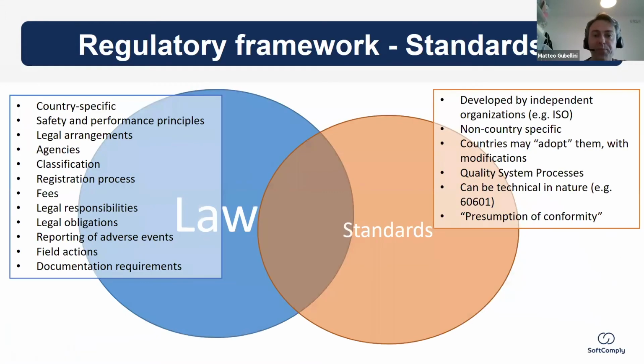It would make sense. So what is different between law and standard? The law is very country specific. It talks about principles of safety and performance of the medical device. It talks about legal arrangements, registration, who the agencies are, how you classify a device, as I said, the fees that you have to pay for different services, the legal responsibilities, who is responsible for what, how to report complaints and adverse events, and the documentation requirements to submit typically for an application.